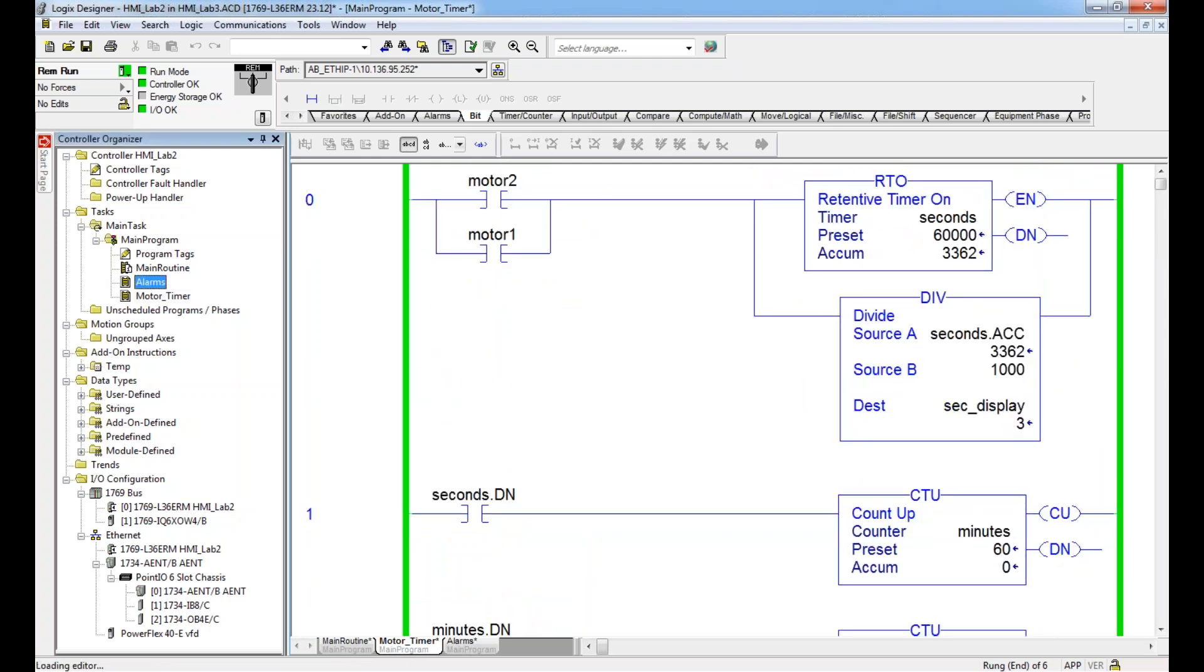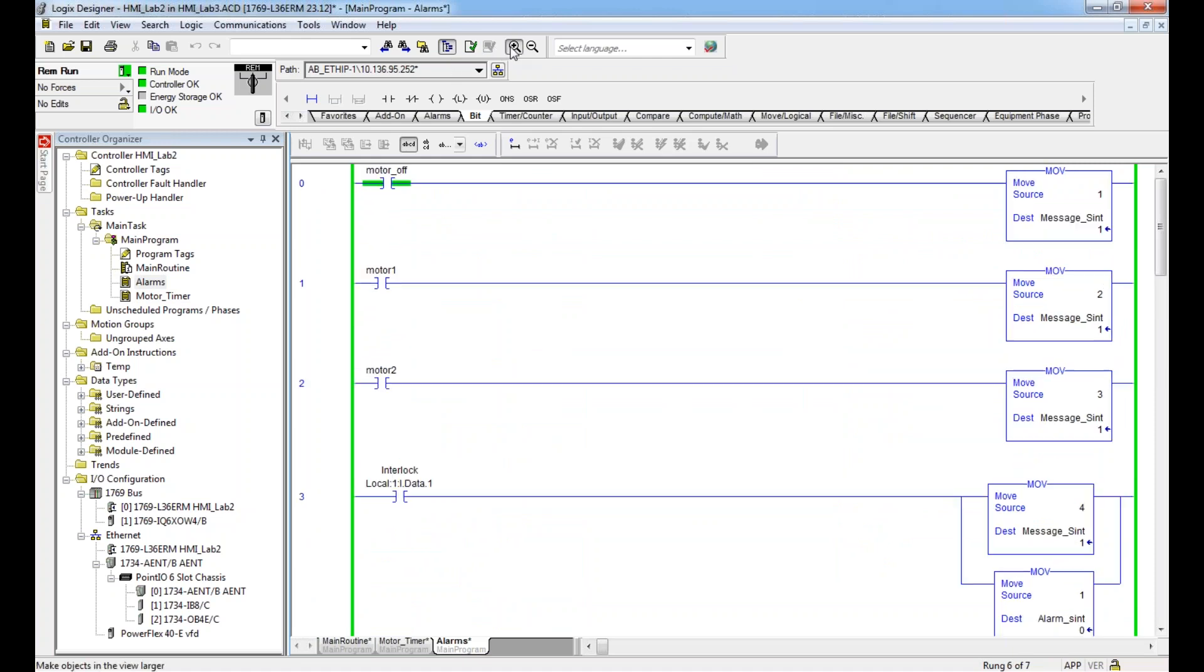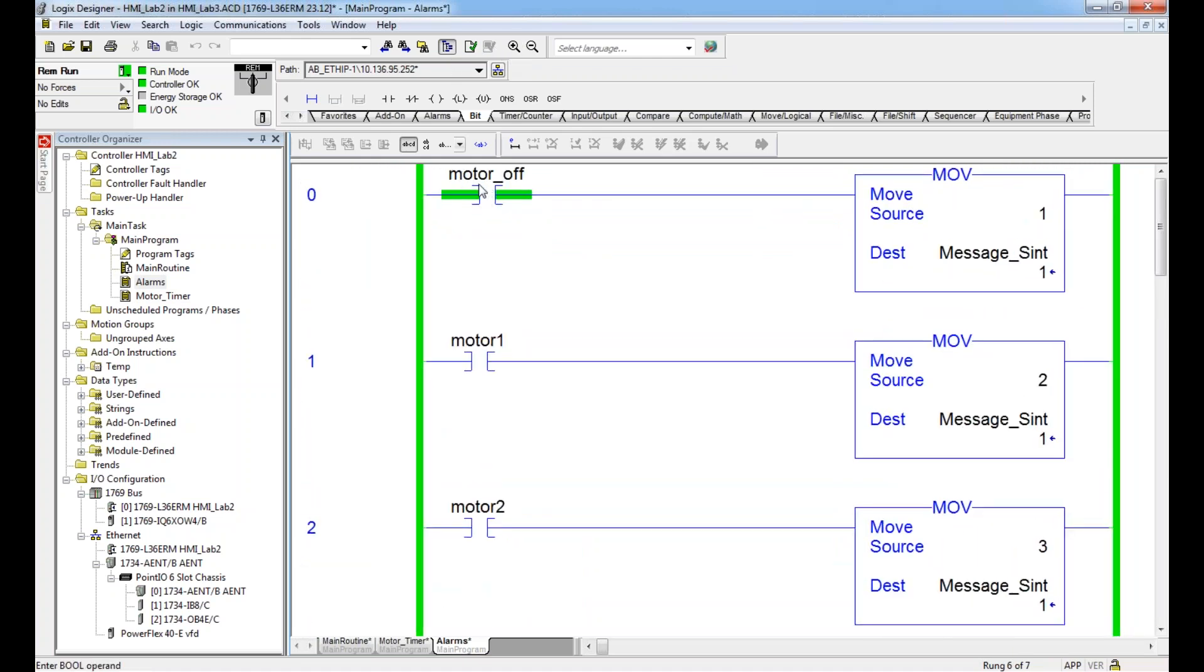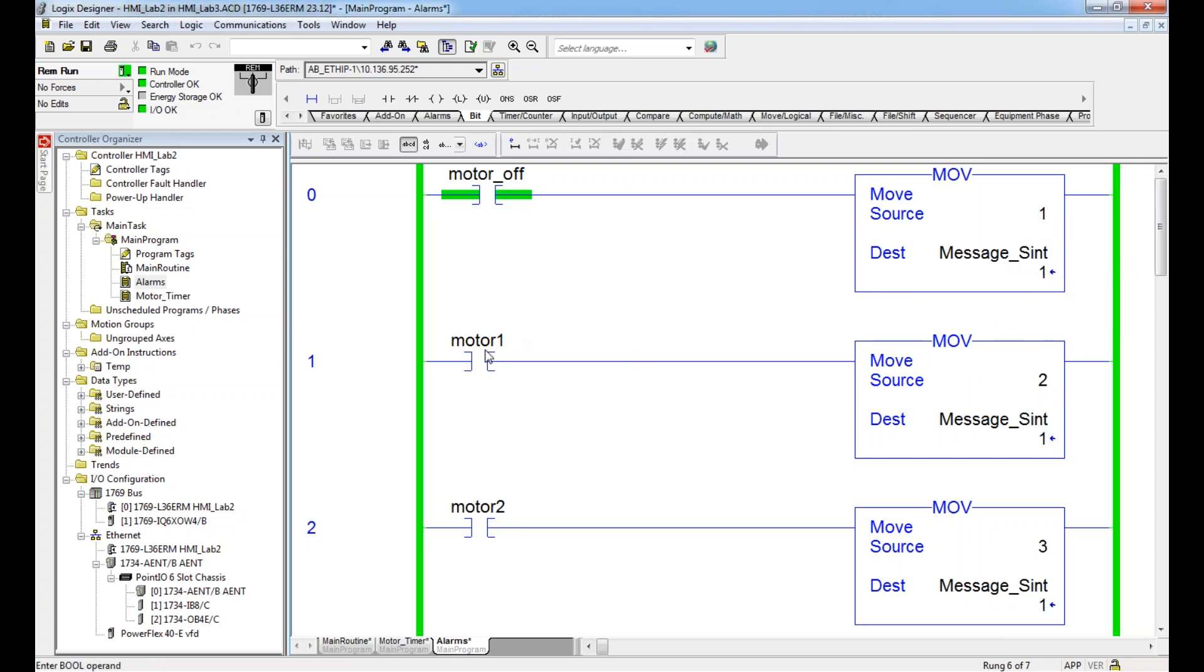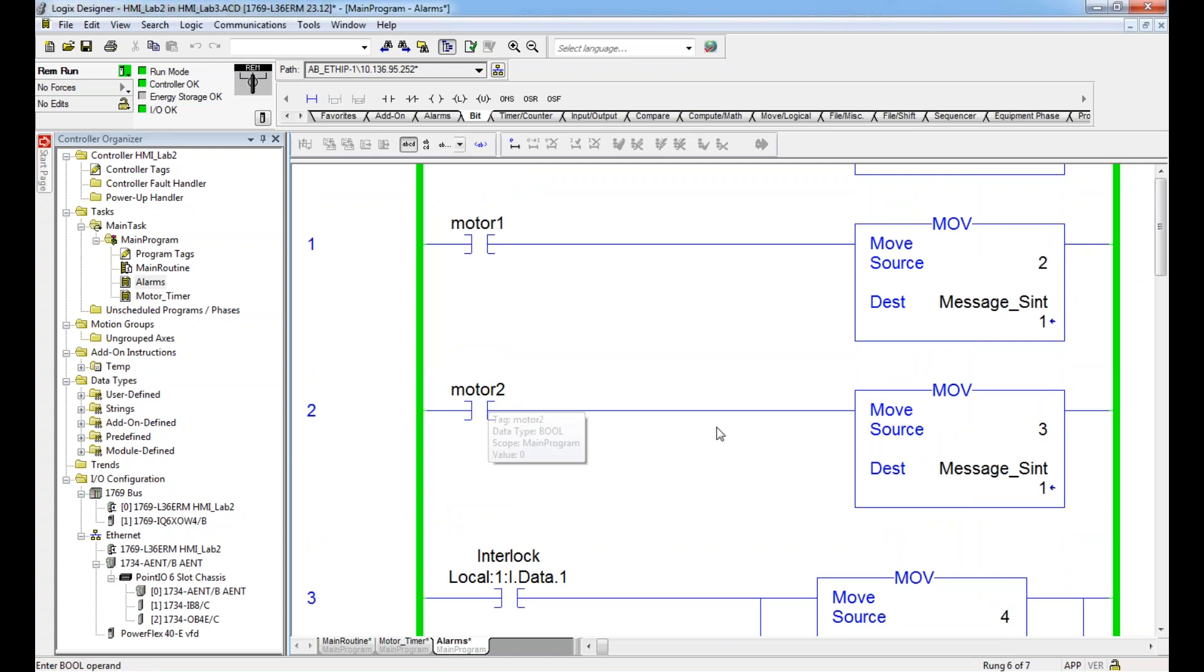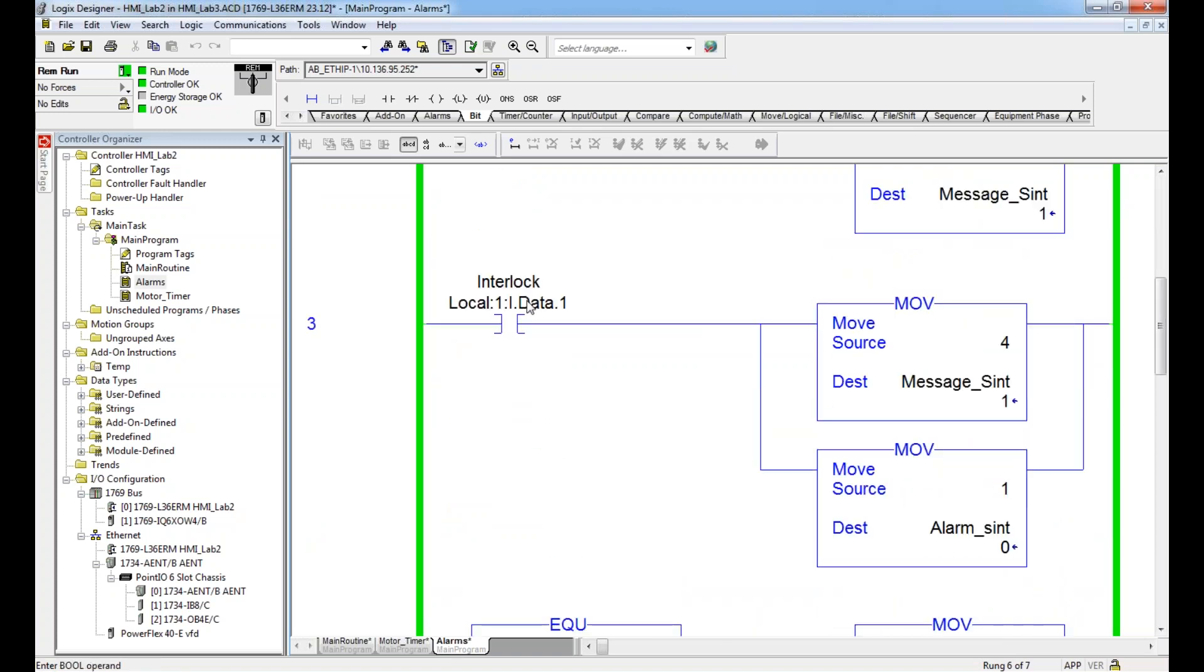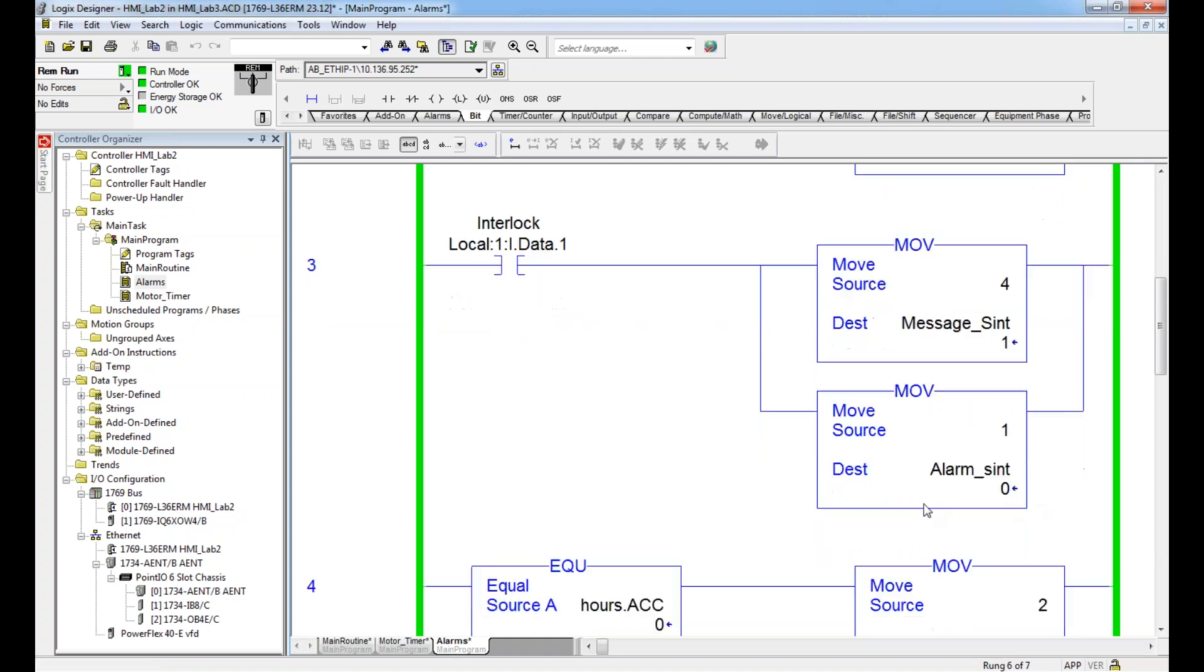I also have an alarm subroutine that's currently running. Basically, when the motor is off, I'm moving a one into a message single integer. This is what's going to change our value on the HMI to tell us what's going on using a message display. You could do this with a multi-state indicator, but the message setup is a little more cleaner and better. So move one if motors off, move two if motor one is on, move three if motor two is on. And then if I have an interlock trip, I'm moving four into the message thing, and I'm also moving a one into my alarm.